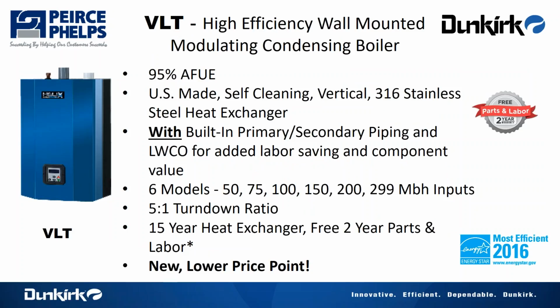So shifting on the condensing platform from the DCB, we want to talk about the VLT boiler, the boiler that's been in the line for some time. Want to hit on its features. We've had some changes on it, most importantly there at the bottom, but 95% AFUE. This boiler has the exchanger that we designed, US-made, self-cleaning, vertical water tube heat exchanger. The VLT has built-in primary, secondary piping and a built-in low water cutoff. So added labor savings, added value, time savings, component purchase values.